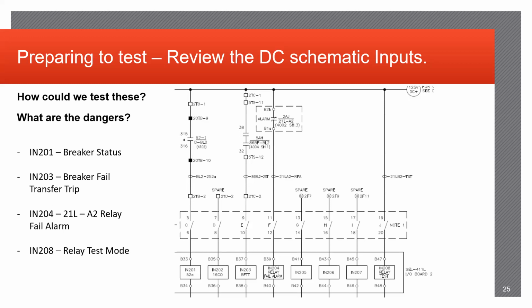As well as the other side of it, if the breaker's open and your relay thinks that the breaker is closed, it can cause misoperations such as reclosing, triggering open and close functions on the breaker multiple times over, which can again cause damage to the equipment itself. And also, if there is any other form of communication tripping, whether it's to another site or just to a different piece of equipment in the yard, that can open up as well, which can cause loss of power to customers, which the client does not like.